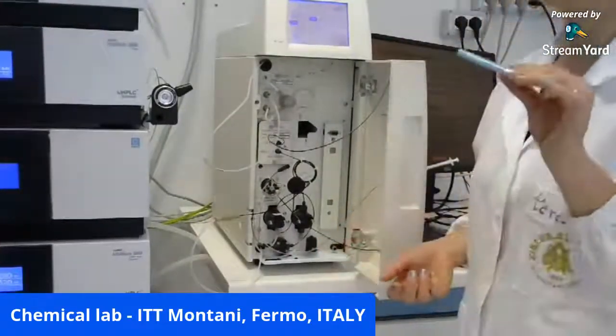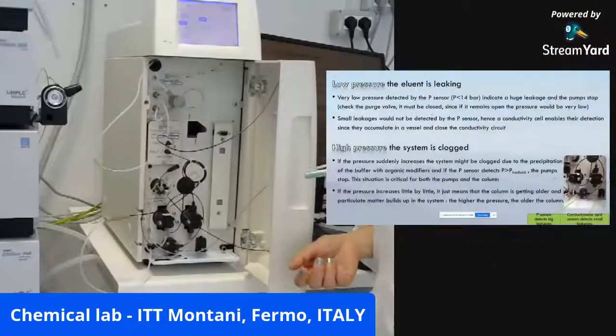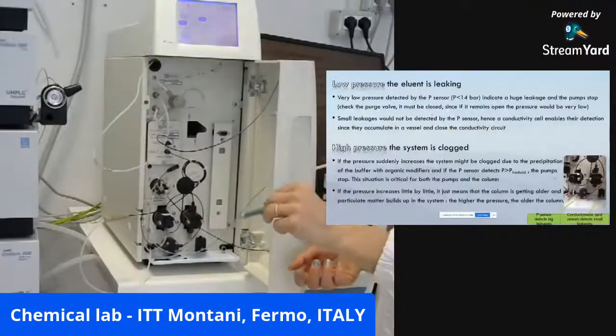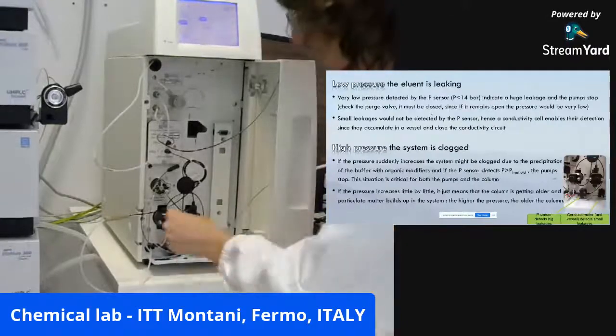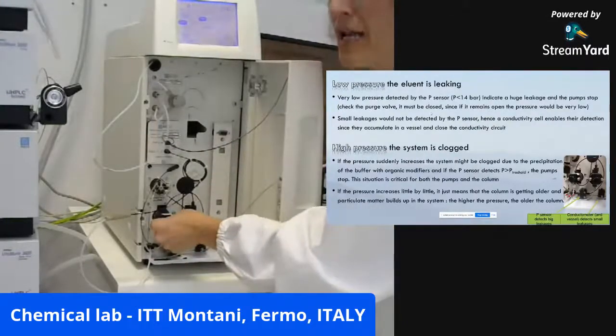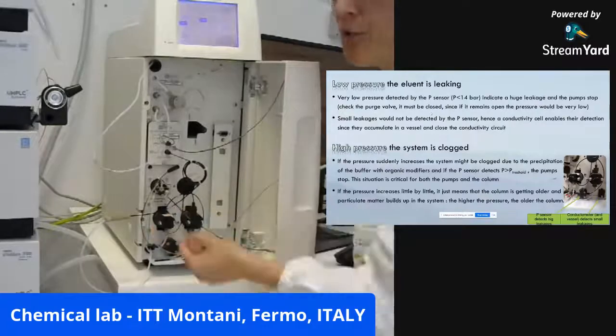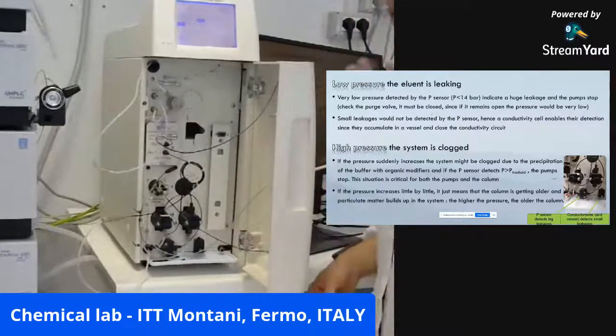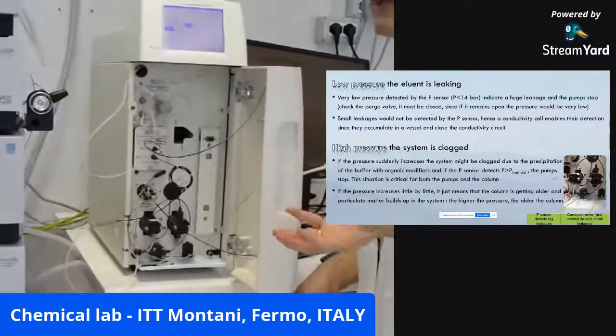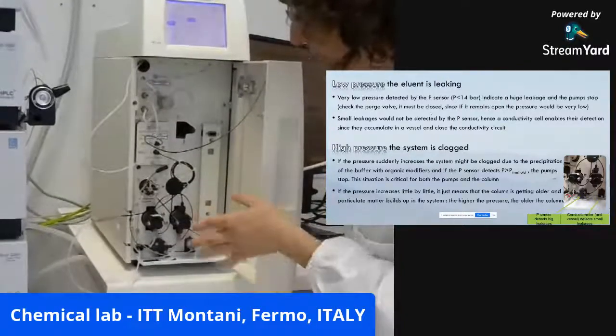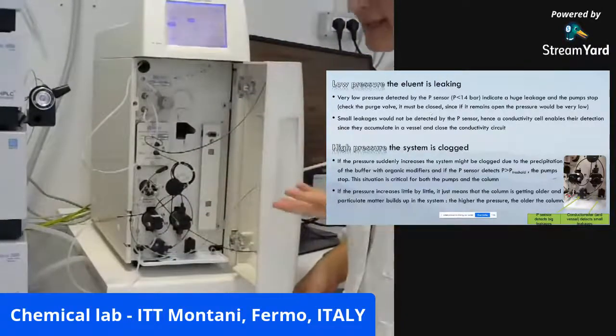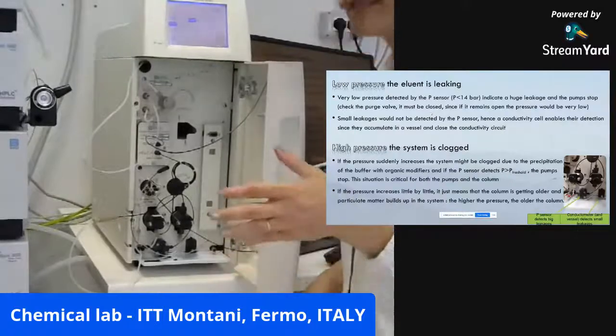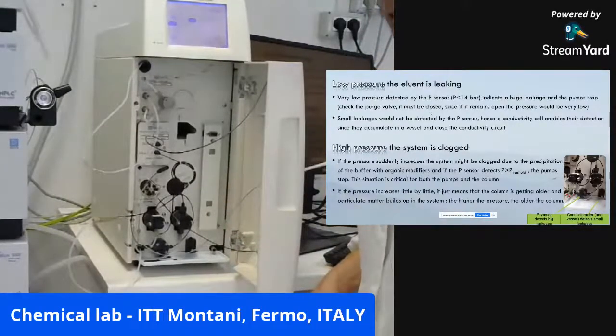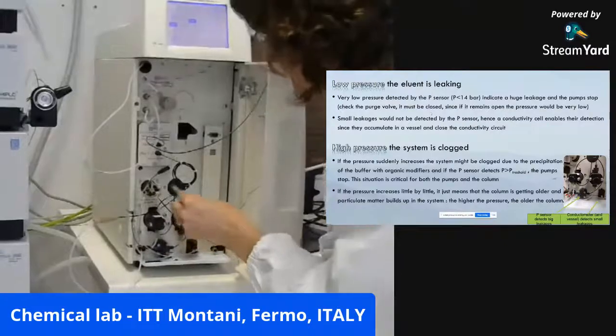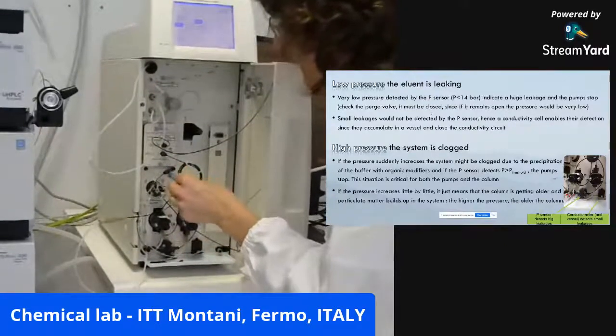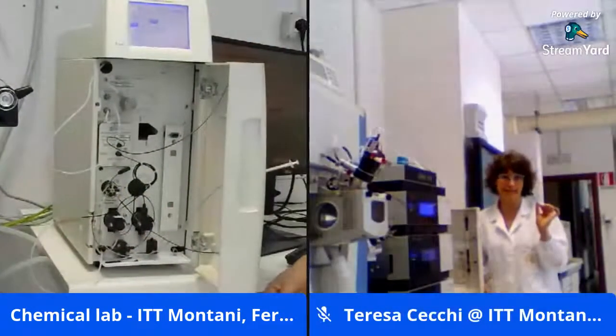What happens if the pressure is too low? Again, the pump would stop. Probably you have left the purge valve open after the priming procedure. You forget to close it and the pressure is very low. In this case, the system alerts us again and would stop the pump because the flow is not the set point flow. But what happens if there's a very small leakage?